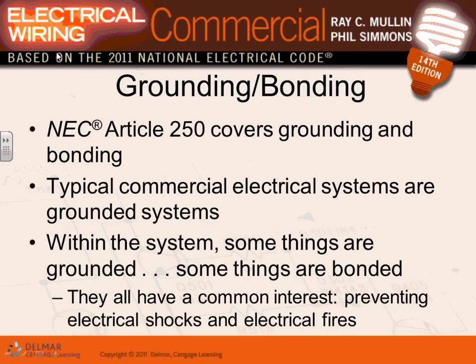Let me just say a few things about grounding and bonding. I'm going to summarize grounding and bonding as when you bring your service to your service conductors, you have to bond the neutral to the ground. So you take a wire and you tie it to the water system inside your building. That's called grounding electrode system, if it's reliable. If it's not reliable, you drive 2 ground rods outside and you tie it to 2 ground rods. If you have concrete encased electrodes, foundation with concrete rebars, you tie to them. And the whole idea with grounding a system, the reason why we ground the system, is because of safety.